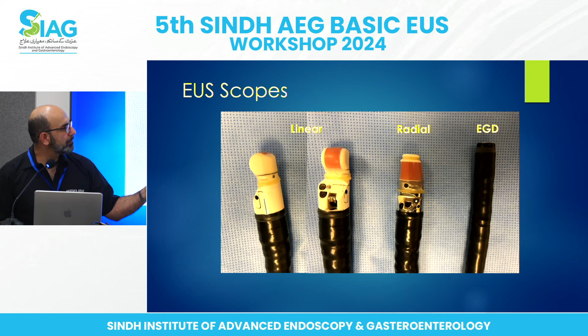Okay, moving on to the scopes. This is important for everybody to have basic concepts about. Linear, radial, and just for comparison, EGD. And the first thing you notice is that the echo endoscopes are much larger than your regular scope. If you look at the diameter, the EGD scope is 9.8 millimeters wide. This is on the Olympus scope. If you look at the radial, the tip is about 11.5, but at its maximum it's about 13.6 to 13.8. And if you go to the linear, even though the tip is 12.6, that's just the insertion point, but at its widest it gets to 14.6.